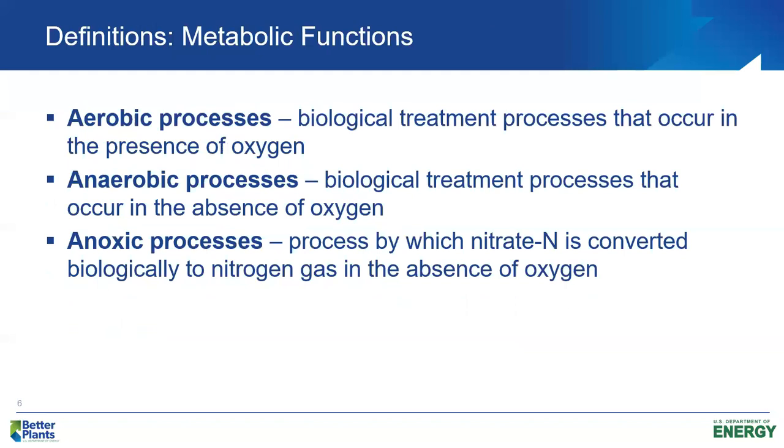Let's talk about the different metabolic functions. We have aerobic processes, anaerobic processes, and anoxic processes. And we'll use all of these depending on what we're trying to accomplish in the treatment plant. Aerobic processes take place in the presence of molecular oxygen. We'll supply the oxygen usually with the aeration system and we'll degrade the biodegradable organic constituents and end up with biomass, carbon dioxide, water, energy, and other end products.